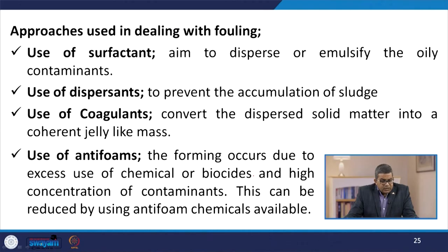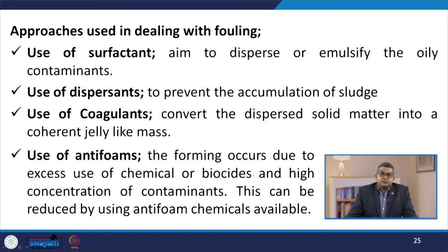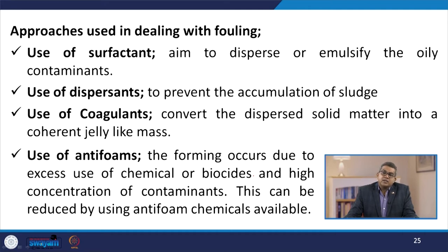There are various approaches to dealing with fouling. One may use surfactants — the aim is to disperse or emulsify oily contaminants. Another approach is the use of dispersants to prevent the accumulation of different types of sludge. Then there is the use of coagulants, which may convert dispersed solid matter into a coherent jelly-like mass. Anti-foams may also be used — foaming occurs due to excess use of chemicals or biocides and high concentration of contaminants, and can be reduced using anti-foam chemicals.